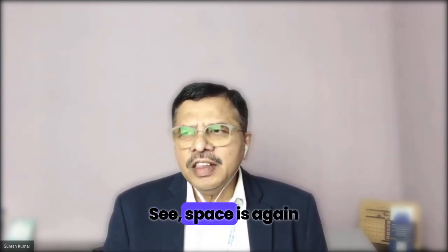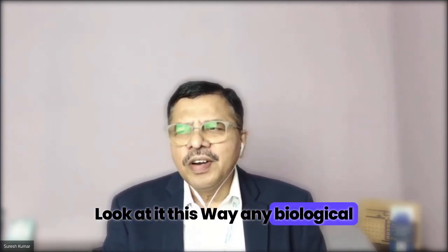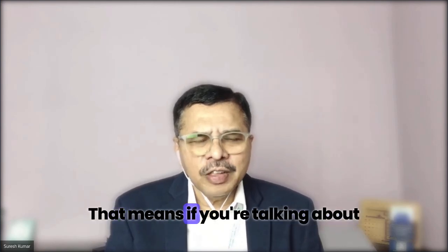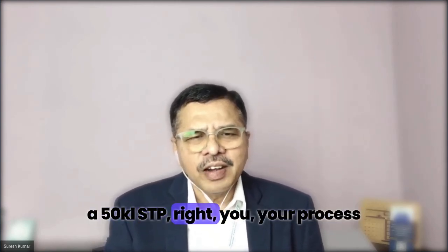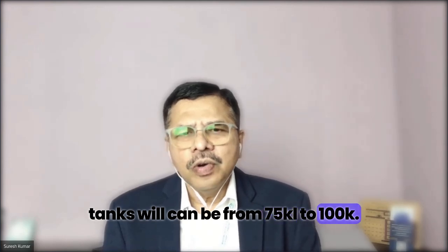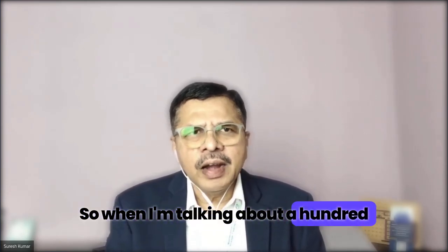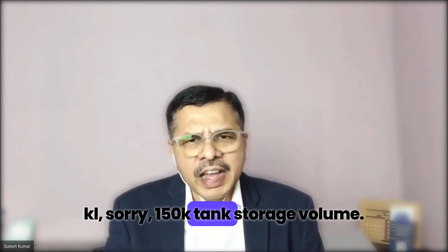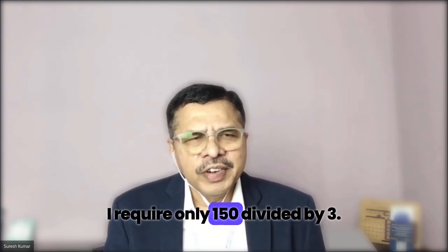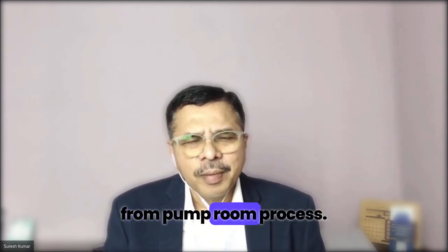See, space is again a question of depth, right? Look at it this way. Any biological treatment process, you would probably require 100% volume to 150% volume. That means if you're talking about a 50 KL STP, your process tanks can be from 75 KL to 100 KL. I'm talking about liquid level. So when I'm talking about a 100 KL, 150 KL tanks storage volume, if I take an average depth of 3 meters, I require only 150 divided by 3, 50 square meters of land is sufficient for me. I'm talking apart from pump room, process tanks.